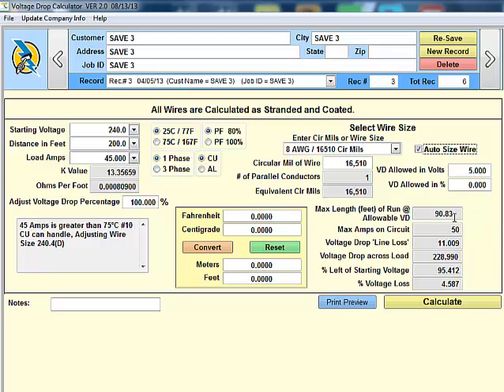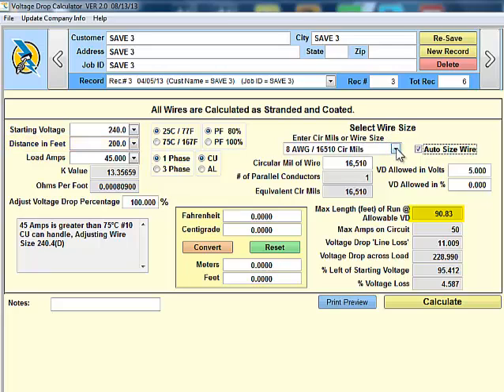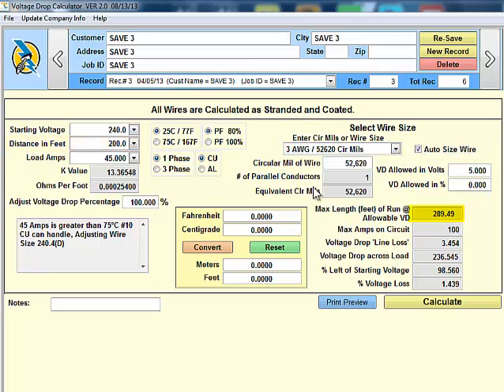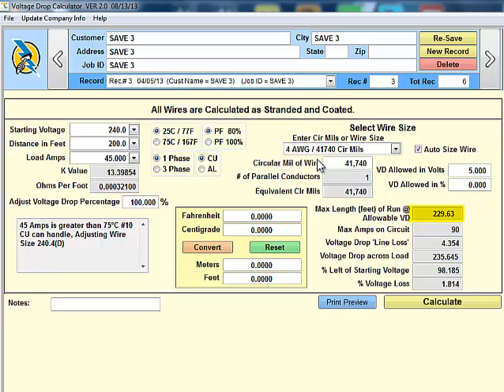That will allow us to go 90.83 feet. But we wanted to go 200. So, let's go ahead and increase our wire size to 3 American gauge. We overshot it there. Let's decrease it to 4. That's about as close as we're going to get. So, to have a 5 volt voltage drop.